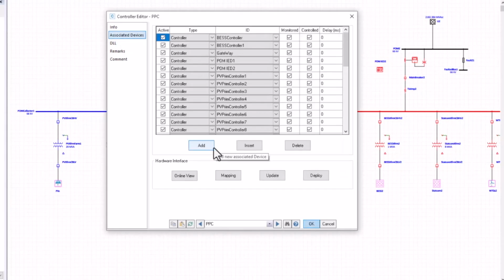Once the DLL is loaded, we must associate the relevant devices with PPC. Navigate to the Associated Devices page and assign elements that PPC will monitor and control. PPC primarily interacts with the other controllers rather than directly with the generation assets. For example, it communicates with the PV controller, which then in turn controls the PV elements. So PV controllers should be associated here.